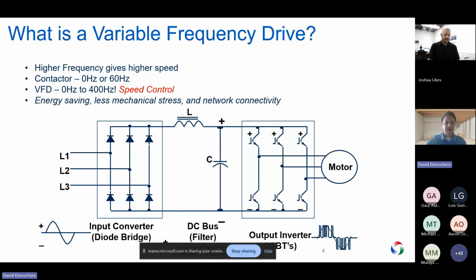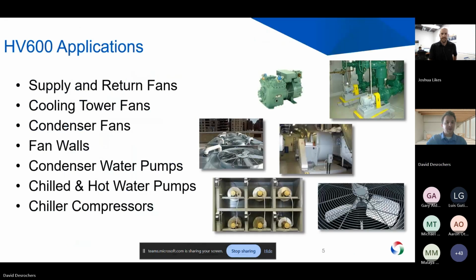If you have a permanent magnet motor application, it's a good idea to consult us for specific parameters, but generally we can control them just fine. The applications for this HV600 product are going to be any fan or pump type application that we were discussing. So supply and return fans, your cooling tower fans, fan walls, all the way down the list to your pumps and finally your compressors as well. Anywhere you really have a spinning motor, we can use a variable frequency drive to operate it.